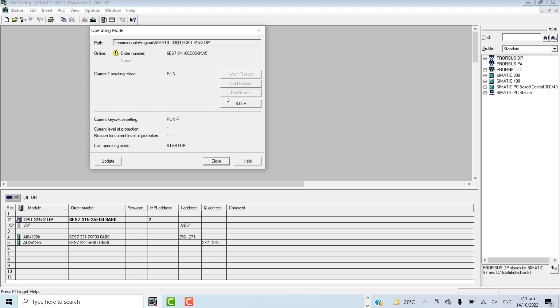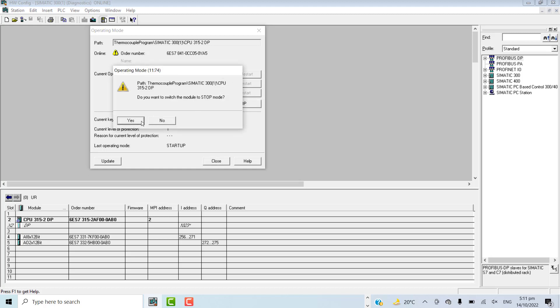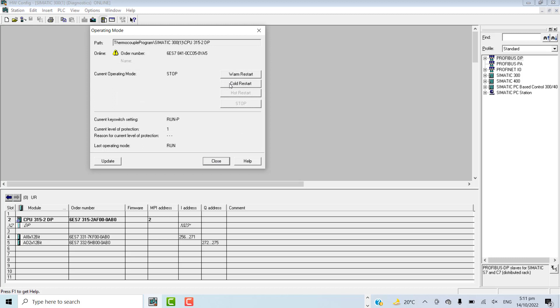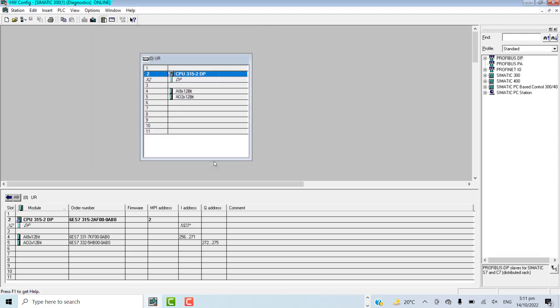If the problem still persists, I can go for cold restart, and that will wash away the entire program from the PLC CPU. Obviously, once the program is washed, you have to re-download the entire configuration: hardware configuration, network configuration, and PLC CFC or ladder logic, or whatever the mode of programming is.